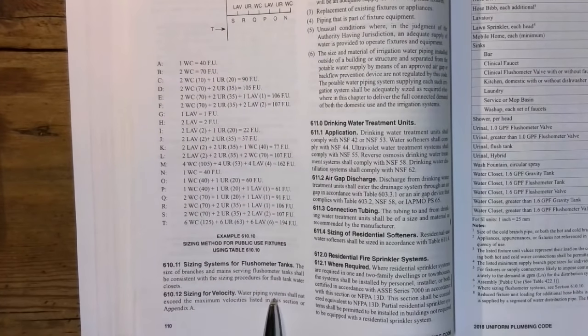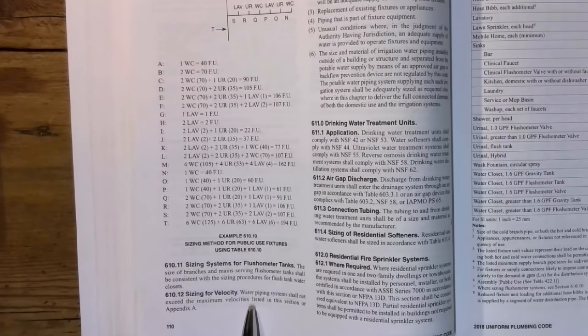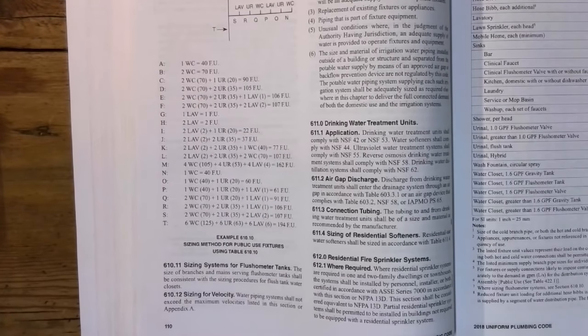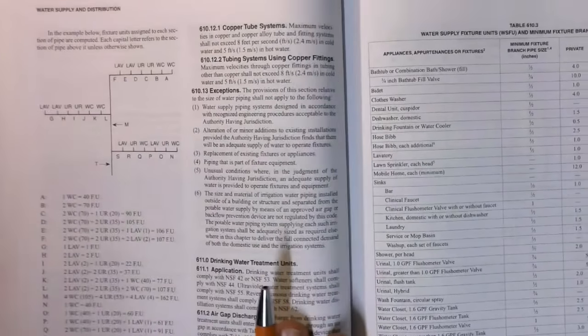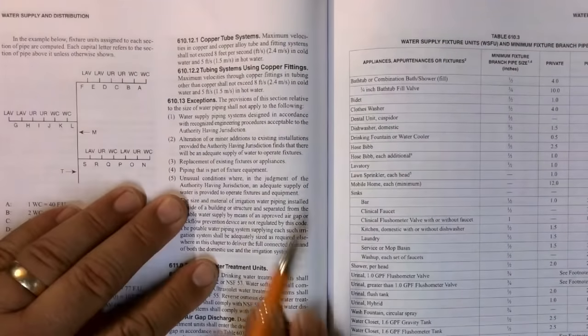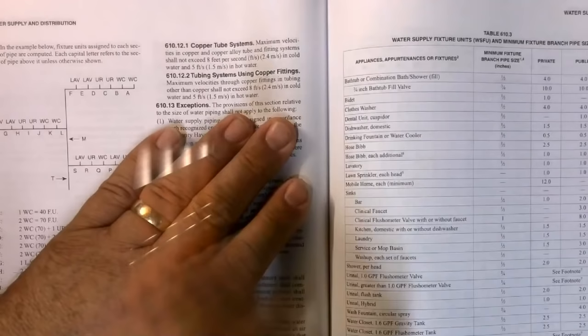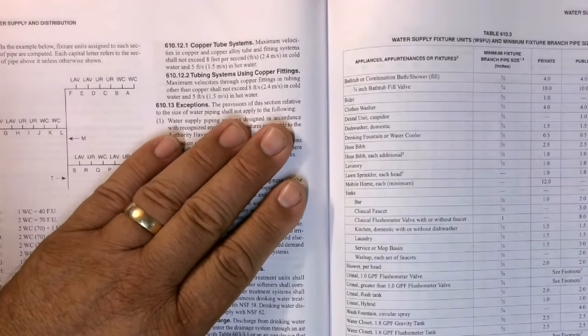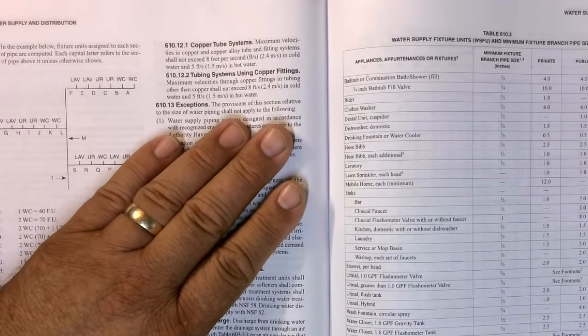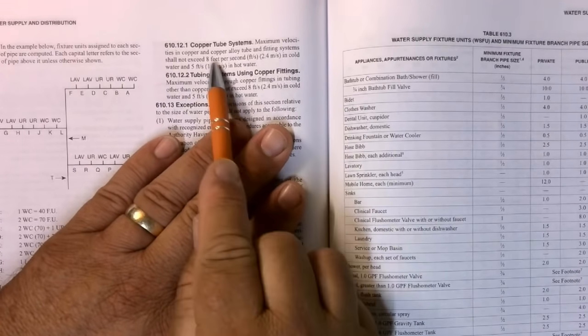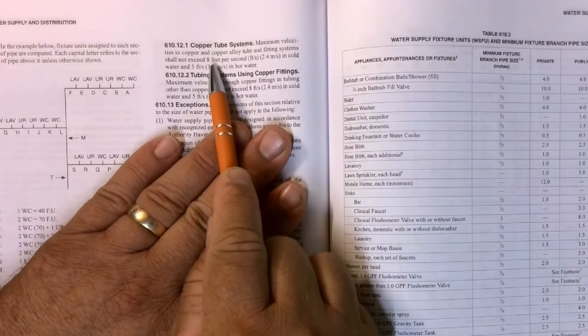Sizing for velocity. Water piping systems shall not exceed the maximum velocity listed in this section or Appendix A. Back up here to copper, right there. Copper tube systems. The maximum velocities in copper and copper alloy tube and fittings shall not exceed 8 feet per second in cold water and 5 feet per second in hot water. That's as fast as we can go through our copper piping, okay?